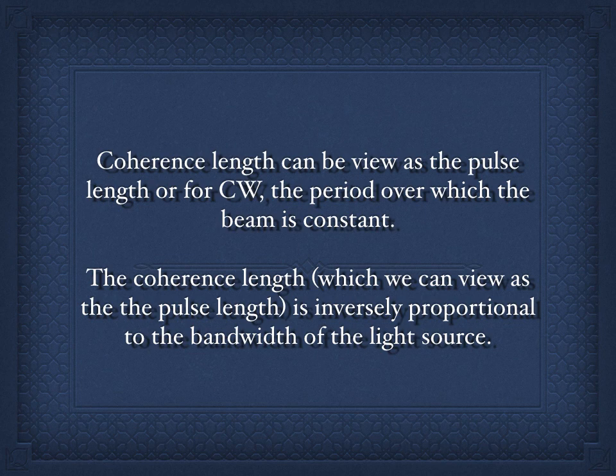When we split the beam and it comes back, it's acting like a pulse because it'll only interfere over that small region where the frequencies and phases of the light within that CW, that constant amplitude beam, match up. Most OCT sources are CW and broad bandwidth, and so they have a very short coherence length that allows very high resolution.